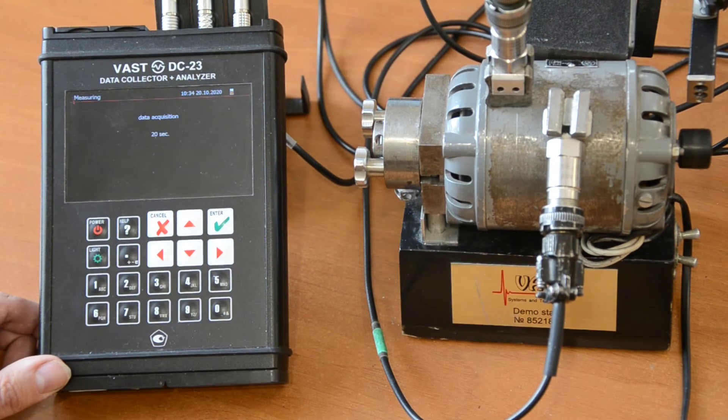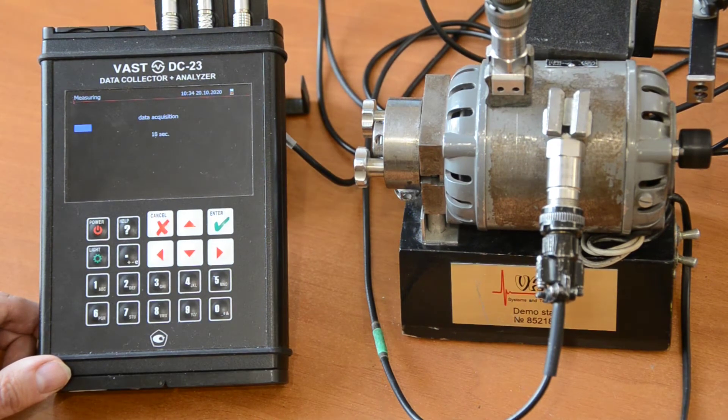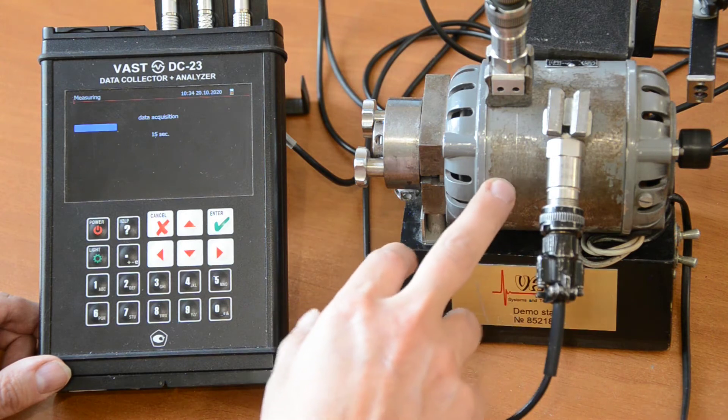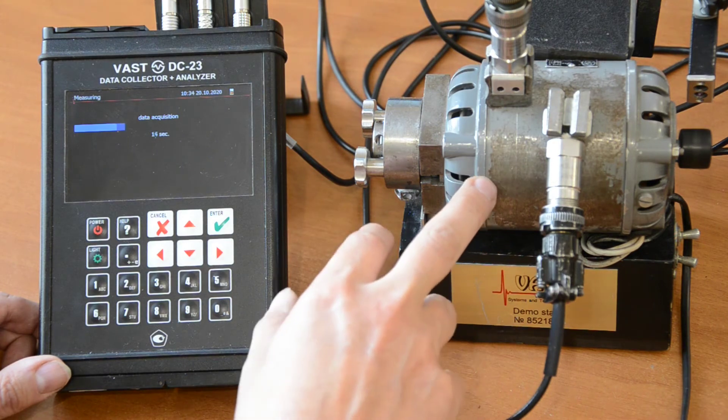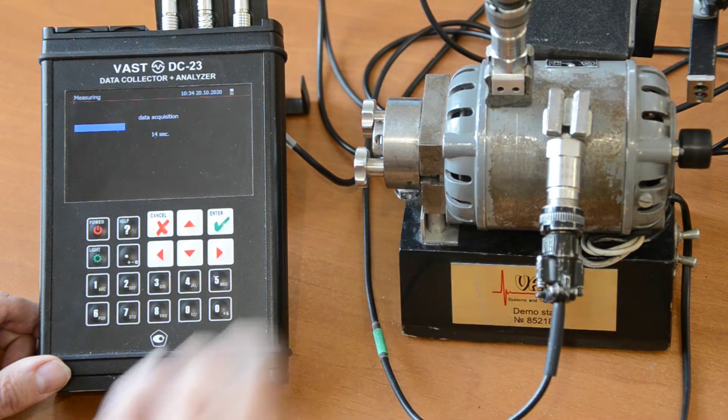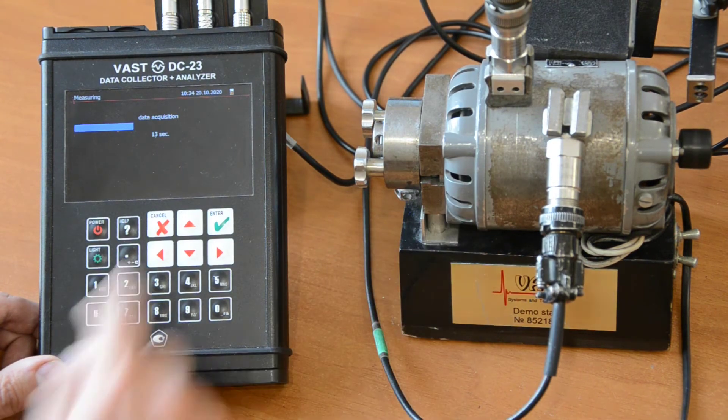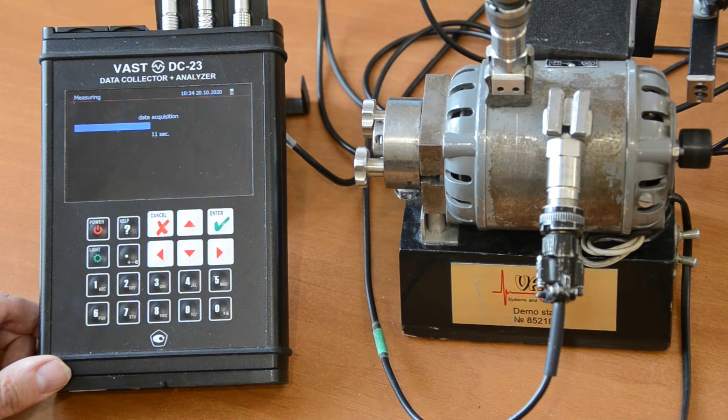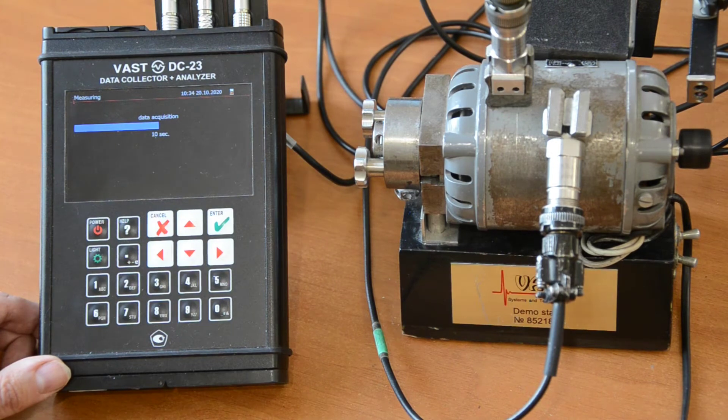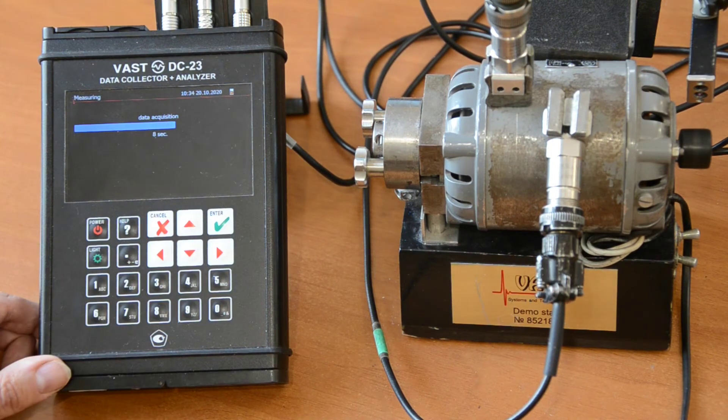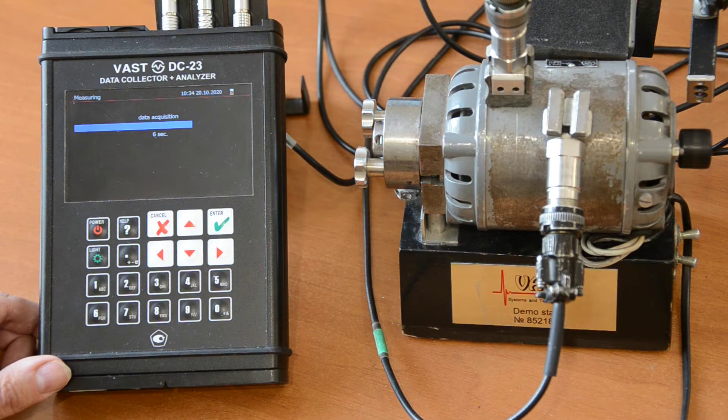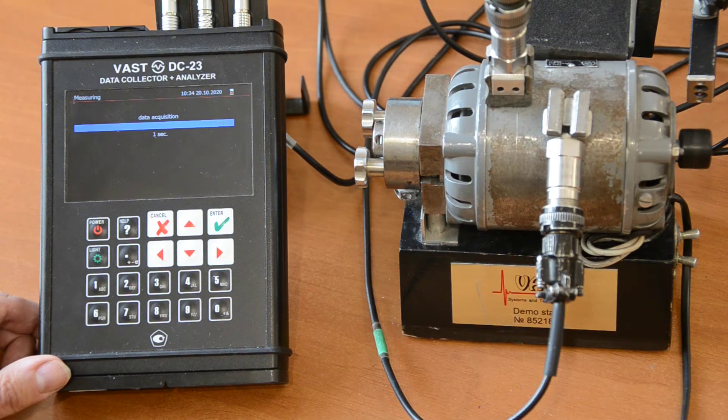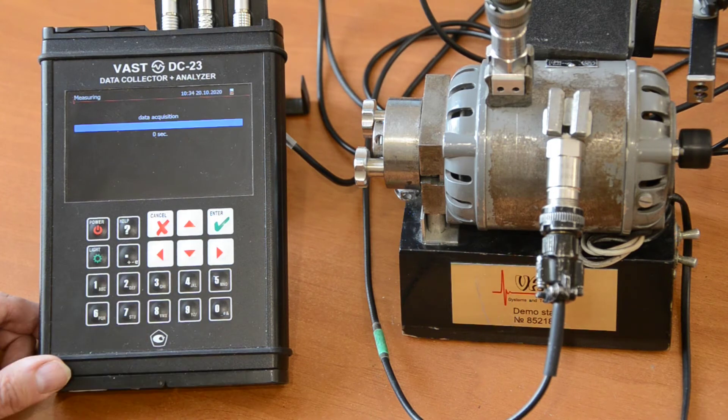It is very important to say that the diagnostics of the induction motor, and here I have an induction motor, it is quite a complicated task. And we have to have very high frequency resolution. That's why we collect data for quite a long time. This is the longest measurement in the vibration diagnostics, I would say. So, it's about 20 seconds.